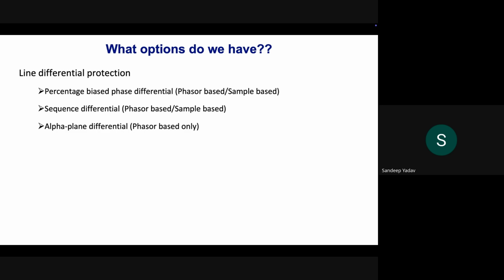No, we will not go into too much detail into this because this is largely protection area, and we would like to keep our focus on the behavior of the protection itself and not into the algorithms that these relays have. So the percentage, I'll just say that the conventional percentage biased differential relays, they do not function that well as compared to the generalized alpha plane differential. So this is one of the algorithms. I would request you to just go through the text and see what's the difference between percentage bias differential and the generalized alpha plane differential. So the relays which employ this algorithm are better as compared to the percentage bias differential.